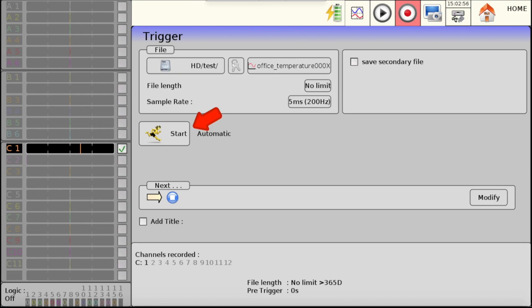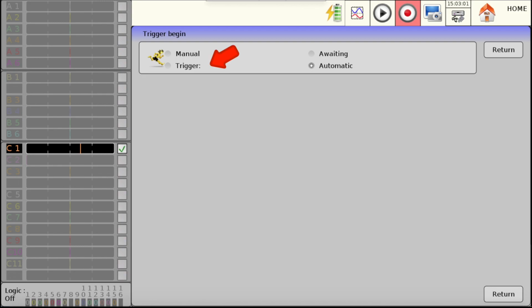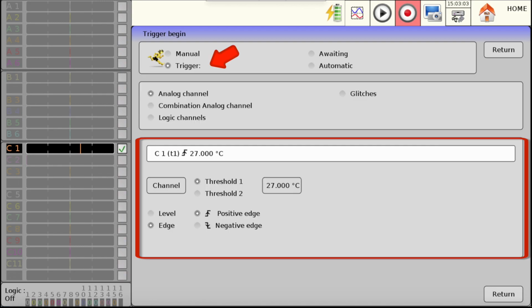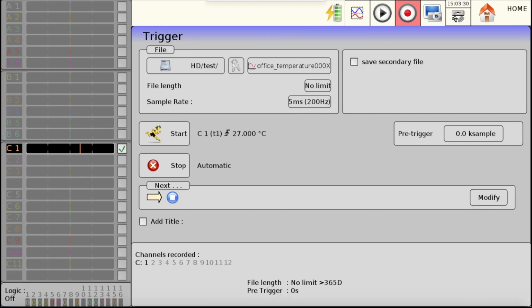Now, let's define the start condition of the data acquisition. We choose Trigger and set the threshold to 27 degrees. To sum up, when the temperature of our C1 channel exceeds 27 degrees, the recording will start. The stop conditions will stay on automatic. In this case, you can stop the recording manually, or it will stop automatically when the internal memory is full. We do not define a next state.